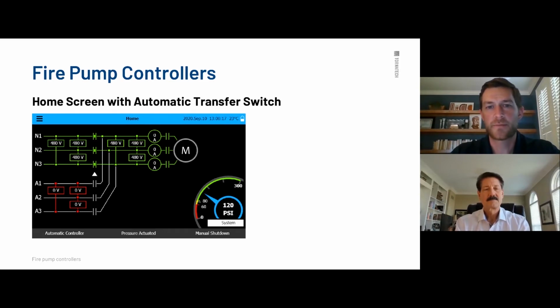This is the home screen with the automatic transfer switch. So you can see it's basically the same thing. We have a lot of similar stuff going on here, except now we have A1, A2, and A3, and where it said L1, L2, L3, it now says N1. So it's just distinguishing between normal power and alternate power. So we're on normal power right now, and this is where the green is easy to follow. You can just see that we're still on normal power. The normal power is healthy. It's still at 480 volts. The contacts there that you can see are filled in. They're closed, meaning that we're on normal power, and you can just follow the flow of electricity all the way over to the motor.